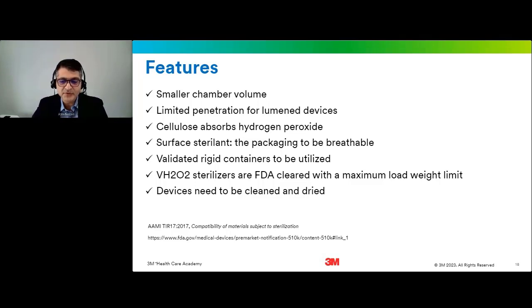For example, in the instruction for use you may read, this cycle is to be selected for a single flexible endoscope with channels with an internal lumen diameter of 1 millimeter or larger, and a length of, let's say, 900 millimeters or shorter. So you will see statements like this that clearly mention what type of instrument with how many channels can be used for that specific cycle within that specific sterilizer model. So definitely follow the instruction for use. Cellulose and its derivatives can absorb hydrogen peroxide. Therefore, enough dose may not be left, and this can affect the efficacy of the process. When products get FDA clearance and get validated to be used in a specific sterilizer, these conditions are all considered.